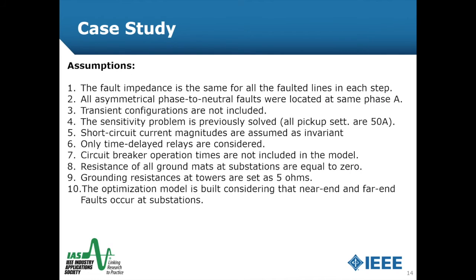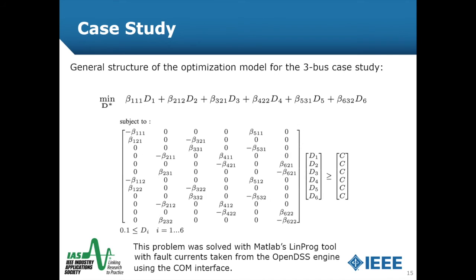There are certain assumptions used in this approach. I will highlight three of them: transient configurations are not included, though we intend to address that in future work; only time-delayed relays are considered, not definite-time relays; and circuit breaker operation times are not included in the optimization solution. This is the general structure of the optimization model for the 3-bus case study, solved using MATLAB's linear programming tool with fault currents obtained from OpenDSS via the COM interface between MATLAB and OpenDSS.